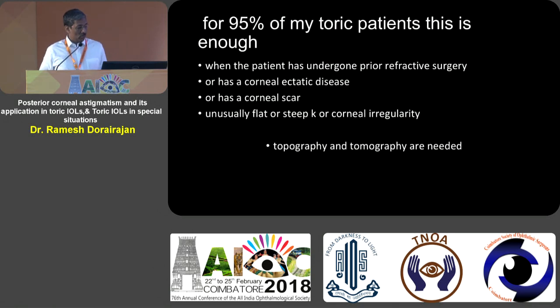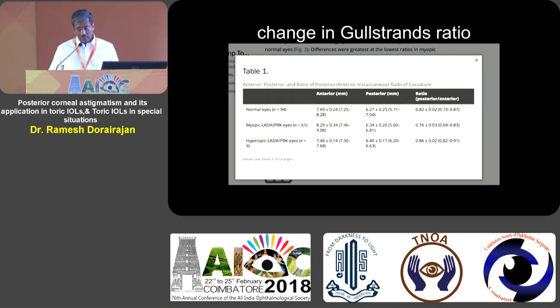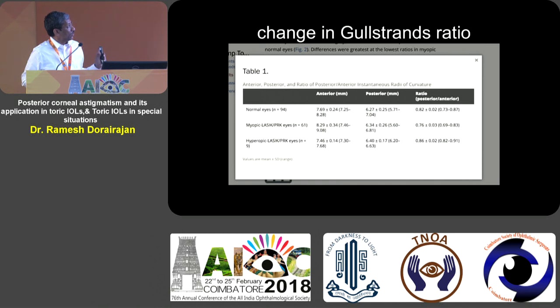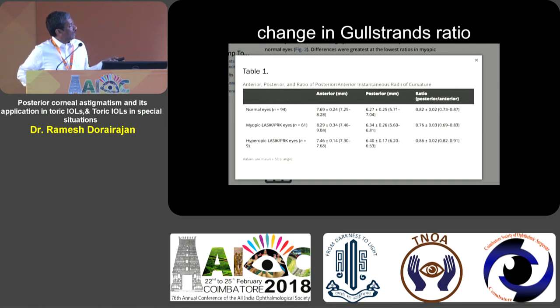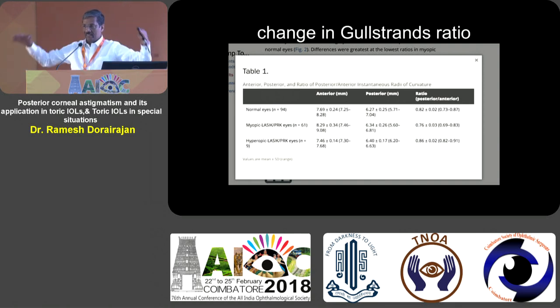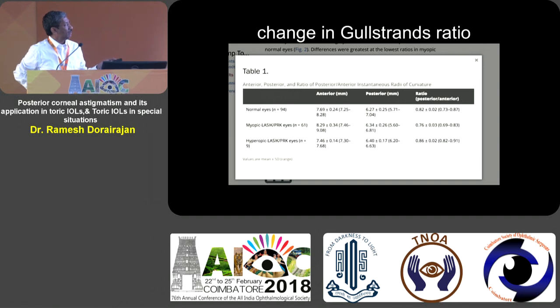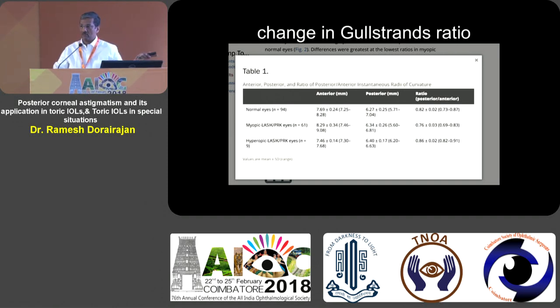We assume a normal Gullstrand ratio of approximately 0.82. So although we measure the front of the cornea, the machine assumes and compensates for the posterior cornea, and we believe the power is all in the front. But you actually have to add front and back. If you do myopic LASIK, what happens is the back remains the same but the front, instead of being curved, becomes flatter. So the Gullstrand ratio is altered — from 0.82 it can become 0.76, 0.75, or 0.74 depending on how much power was corrected on the front of the eye.